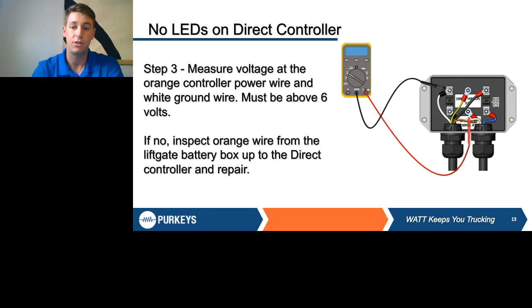If you test it there and it's above 7 volts, meaning good voltage at the front, but you still have no LEDs, you might have a bad controller. If there's no voltage at the front controller but there was at the liftgate batteries, then something has happened along the harness, it might be a cut or corrosion.